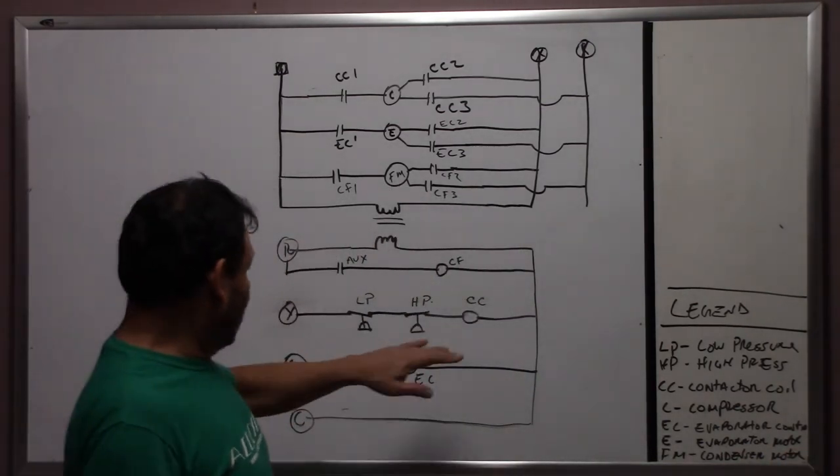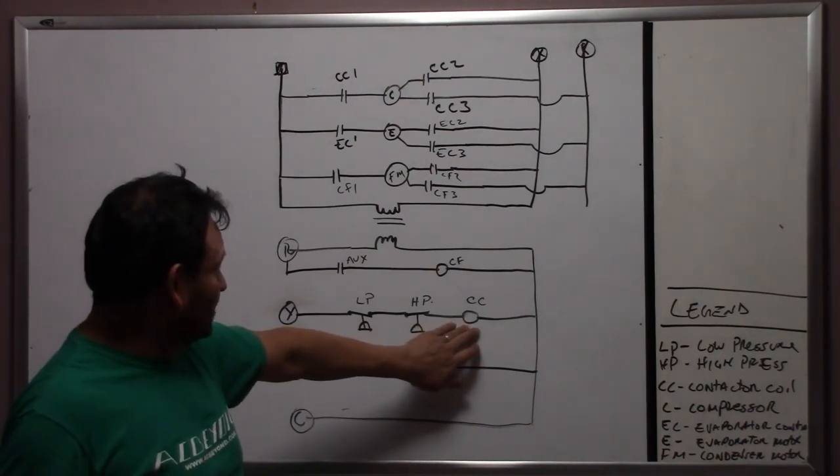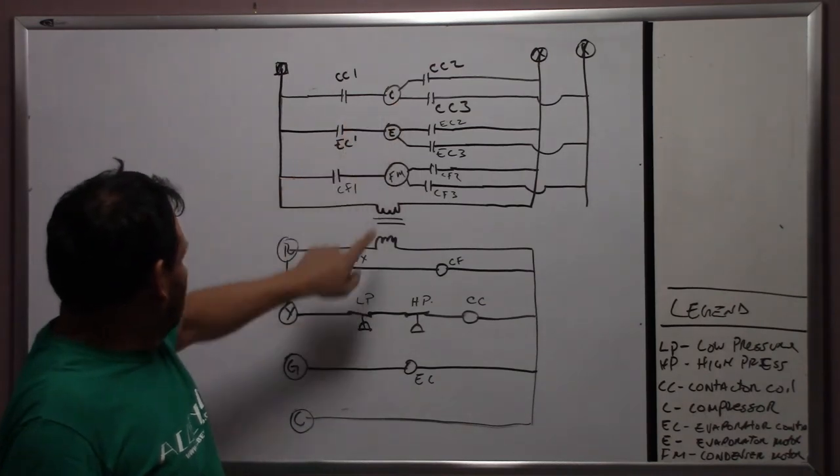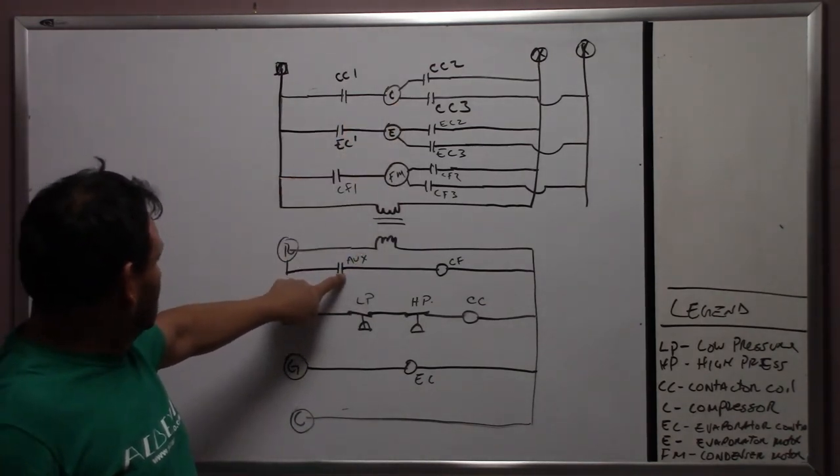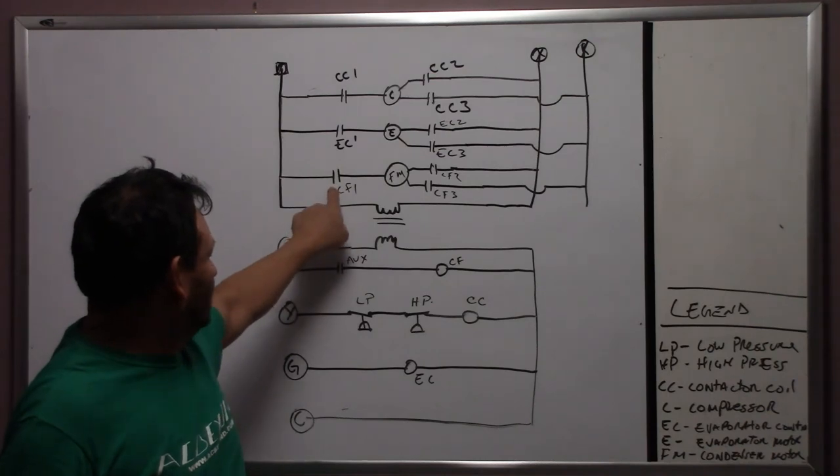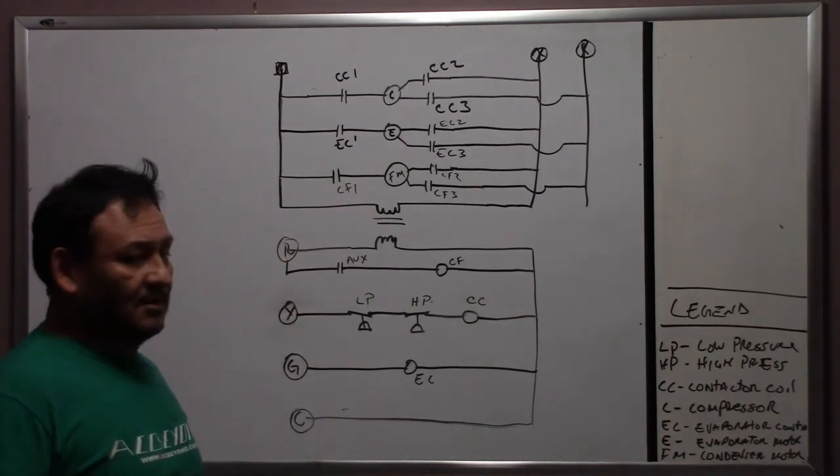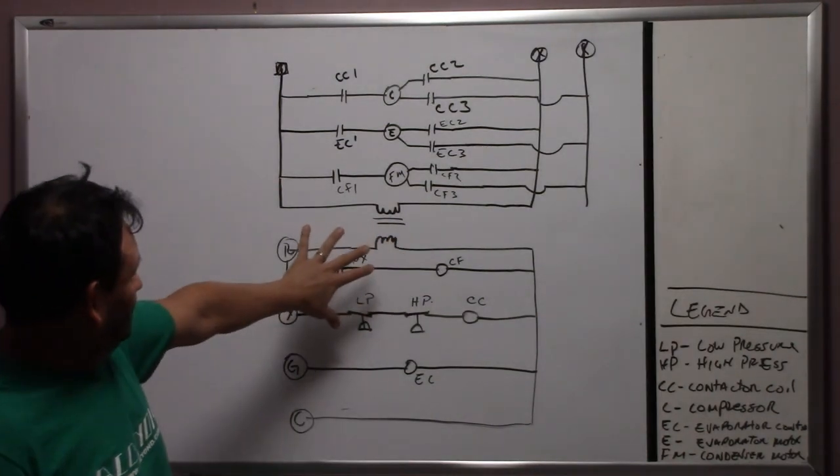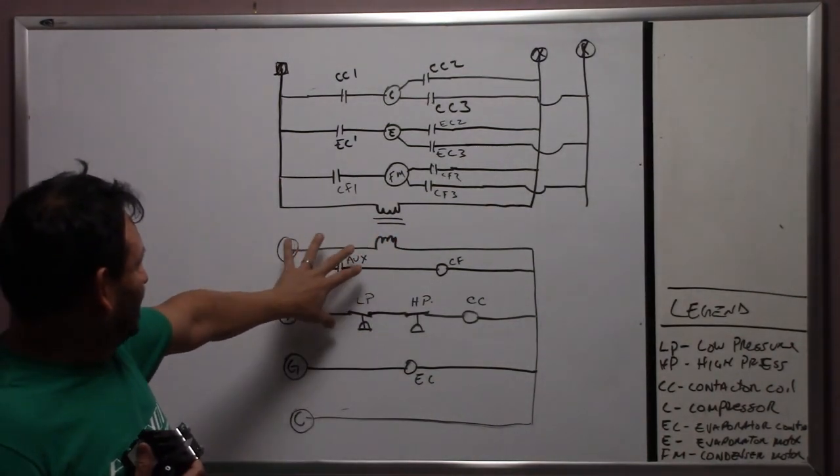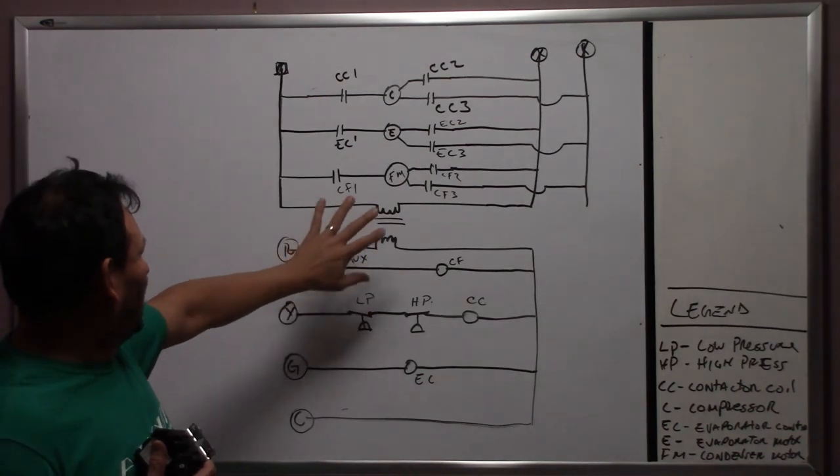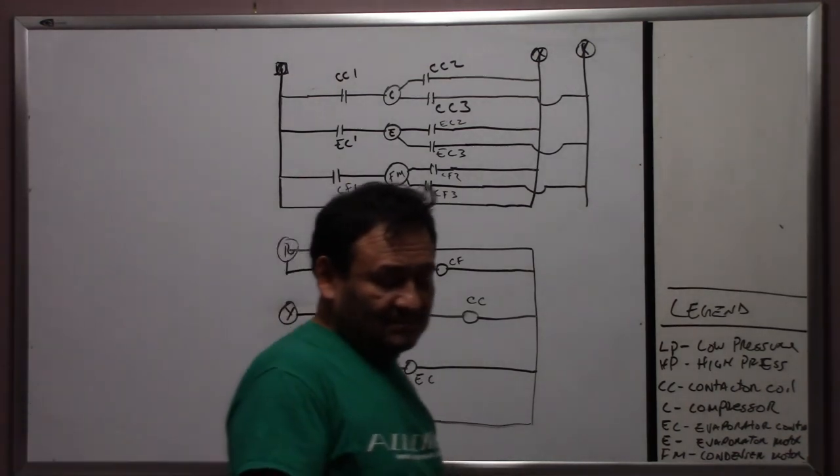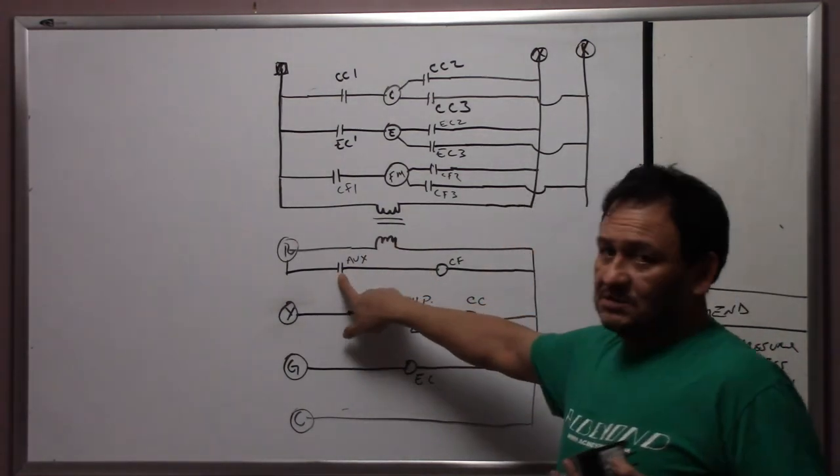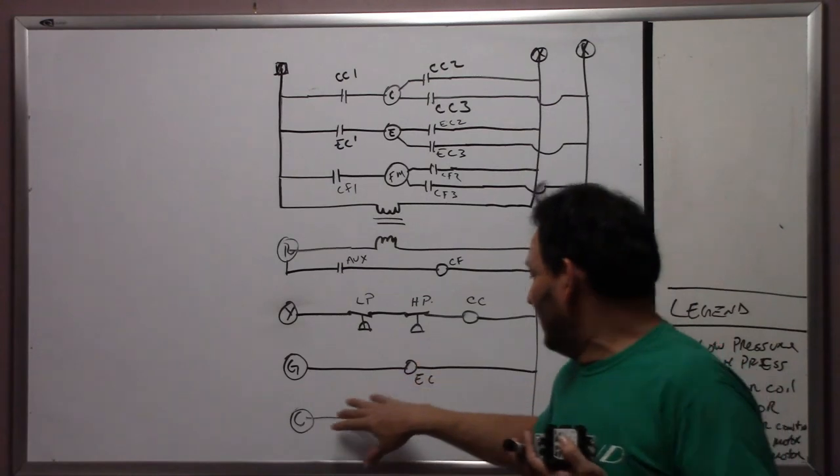So what's going to happen is, like I said before, energize the compressor contactor coil, the compressor comes on, the auxiliaries close, the condenser fan motor comes on. And of course, your evaporator comes on also. But you have to remember that you have to visualize the wiring diagram with no power. You have to think about it, there's no power, so you have to visualize what happens when this closes.